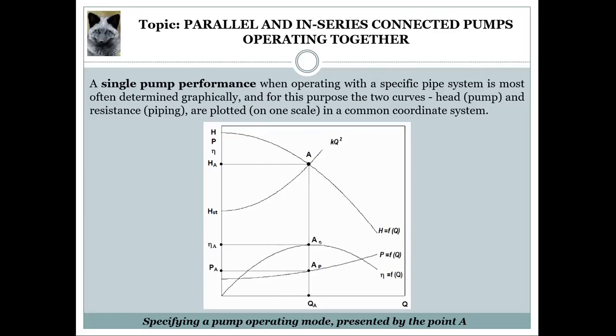Let's talk about parallel and in-series connected pumps operating together. A single pump's performance, when operating with a specific pipe system, is most often determined graphically. For this purpose, the pump head curve and the pipe system resistance curve are plotted on one scale in a common coordinate system, as given in this diagram. The equality of the pump head and the required pressure to overcome the hydraulic resistances is obtained by the intersect point between these two curves, presented by point A.